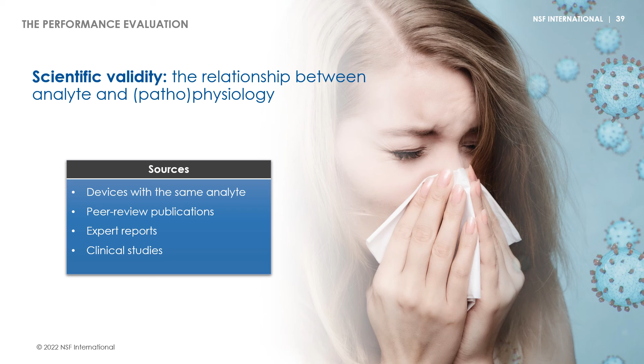This would also consider that your IVD product usually interacts with all sample components, hopefully, however, preferably with the target analyte. With these samples, you may establish the sensitivity of your product for the target analyte, often also referred to as limit of detection. Also, you demonstrate its specificity for the target analyte over other interferences. And as well, you demonstrate the accuracy of your IVD product, meaning how correctly and precisely the analyte is being detected or measured.